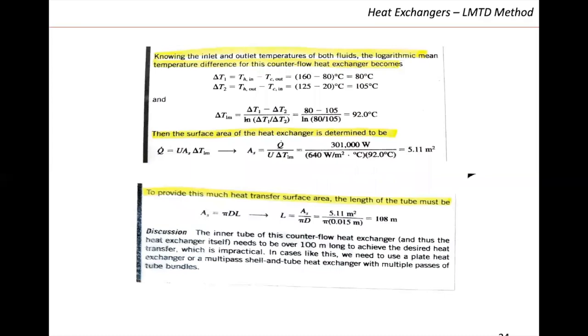Now that we know both inlet and outlet temperatures for the geothermal water and the cold water stream, we can calculate our ΔT. We apply the logarithmic mean temperature difference equation: ΔT1 is hot in minus cold out, so 160 minus 80 equals 80. ΔT2 is hot out minus cold in, so 125 minus 20 equals 105. Then we apply the LMTD equation — (80 minus 105) over the natural log of (80/105) — giving us 92°C.